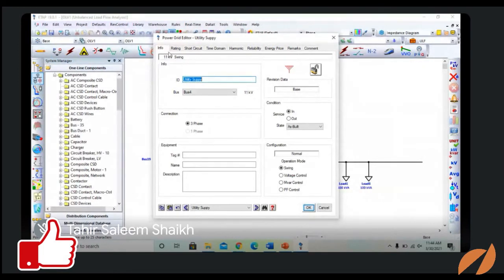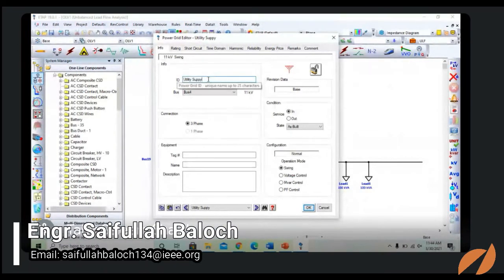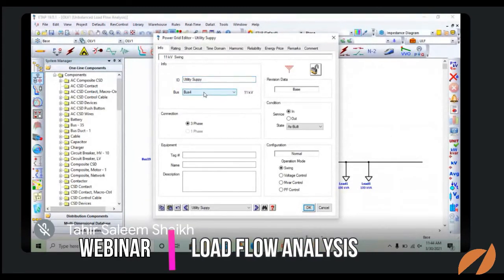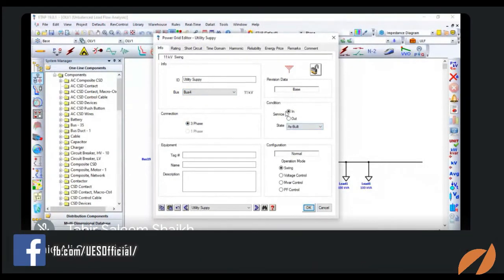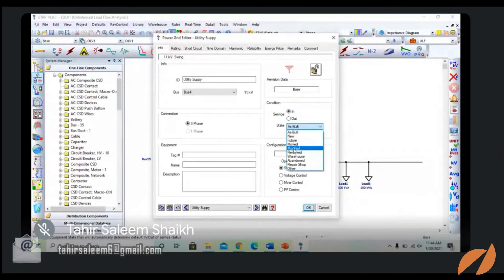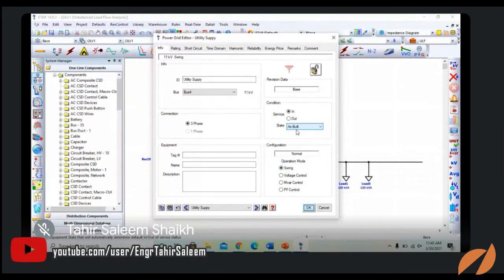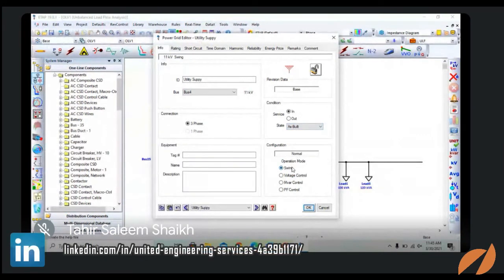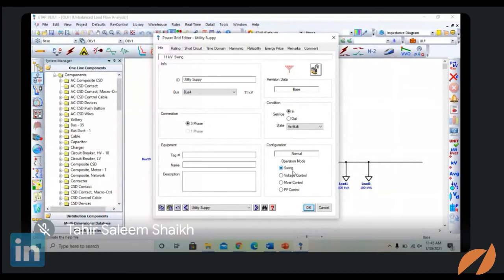So for the power grid, we have an ID. It says that it is a utility supply. This is bus 4, and the connection is 3 phase. This is a 3 phase bus, and the service is in, and the state is new, future, moved, modified, or whatever. For a very typical calculation, we just put this as built. Configuration is normal. For the operation mode, we have swing bus, voltage control, MVAR control, and power factor control. As I've already told you, in the absence of large generators, we are using the grid as a swing bus, so I have just clicked on the swing mode.